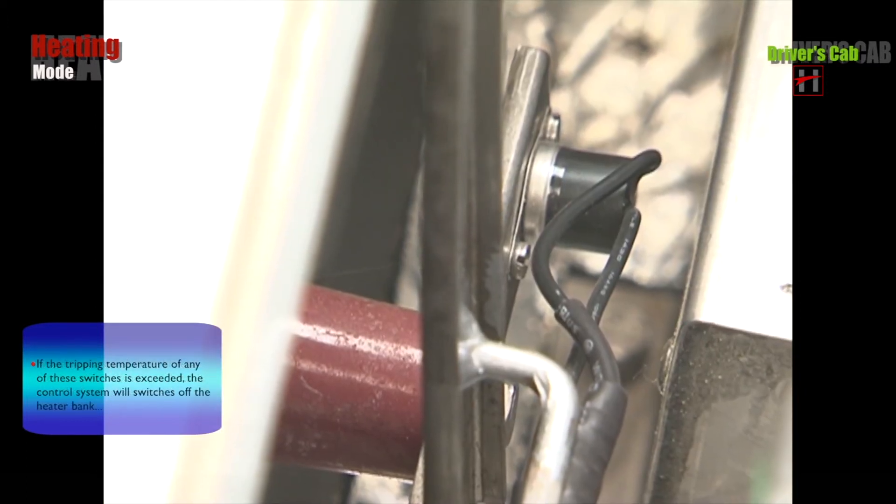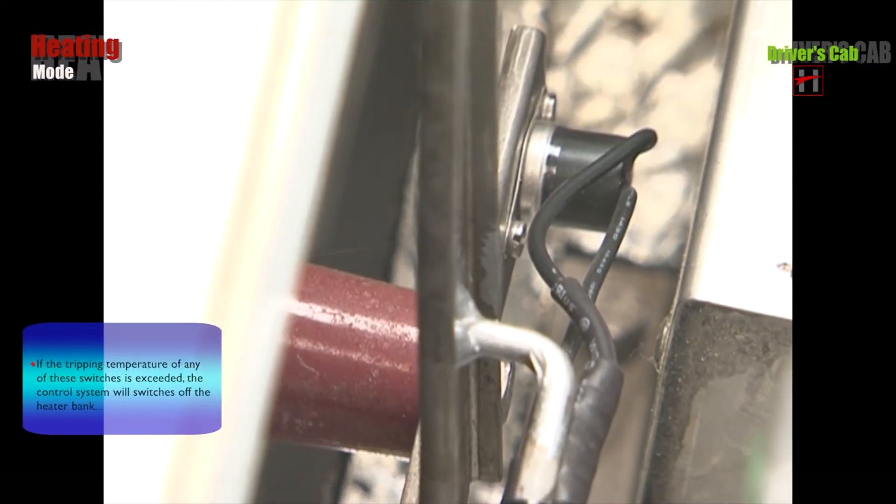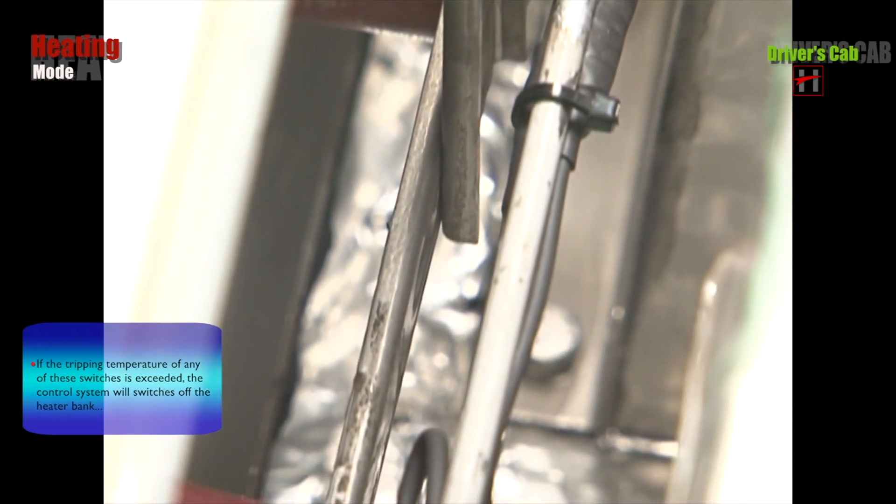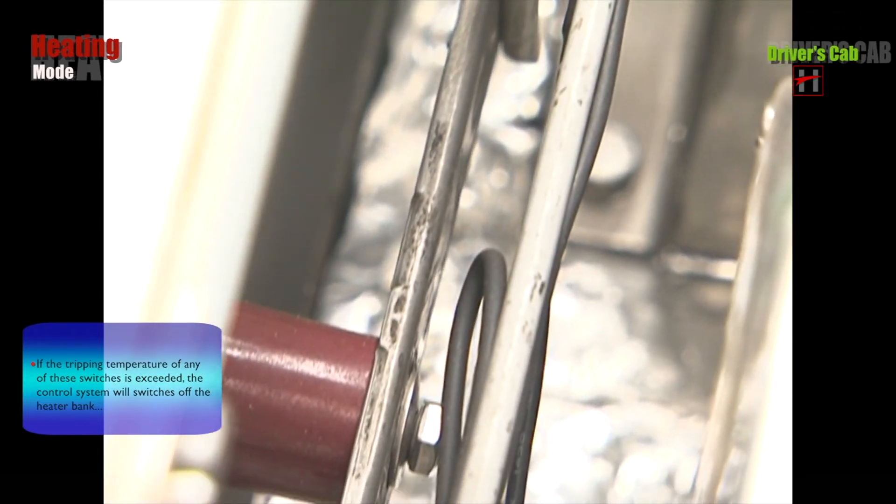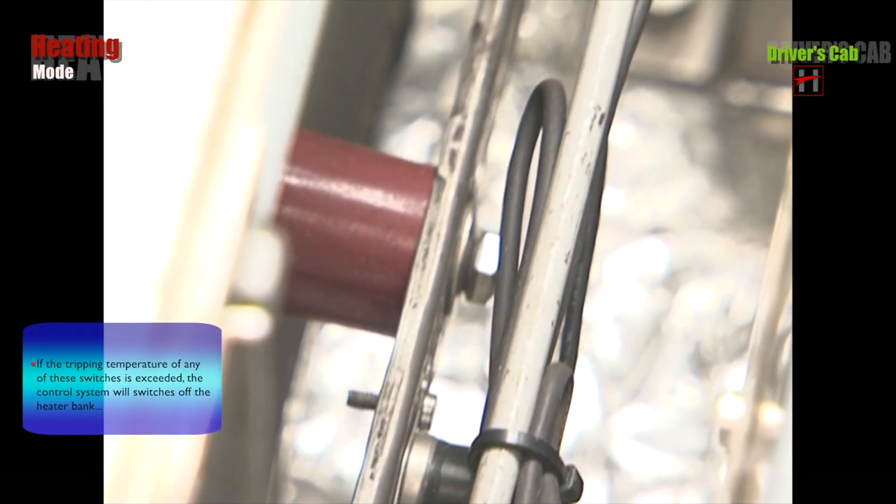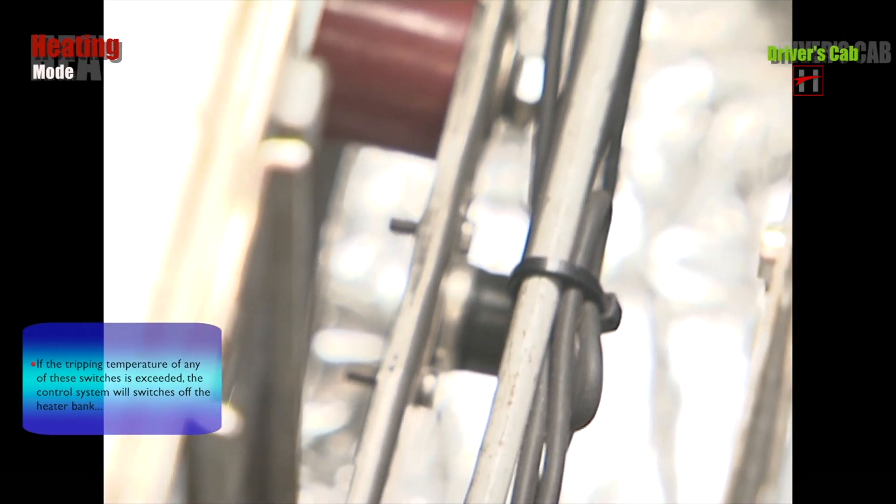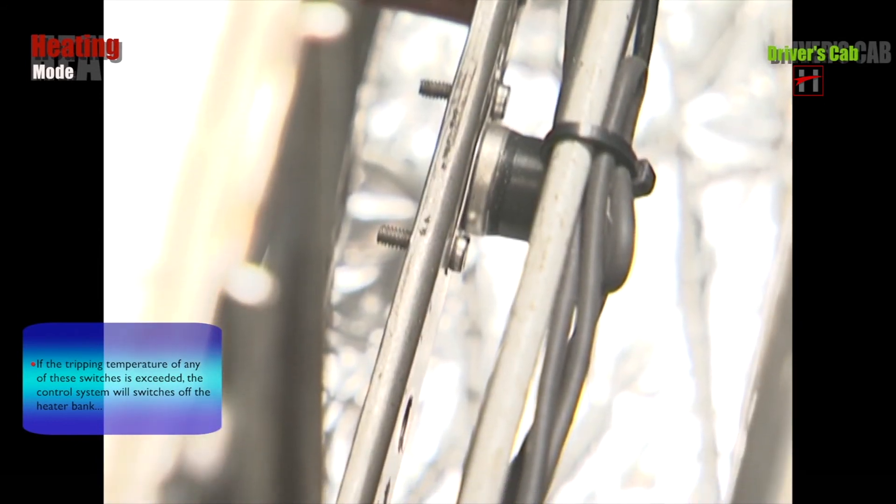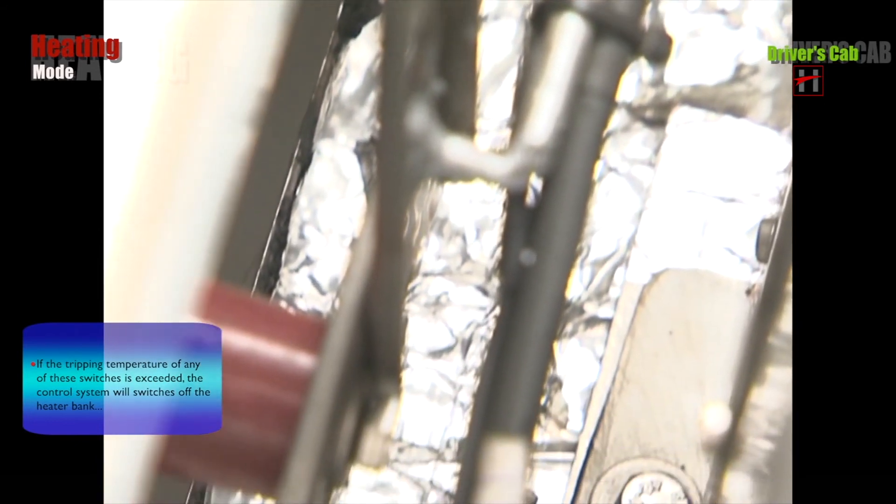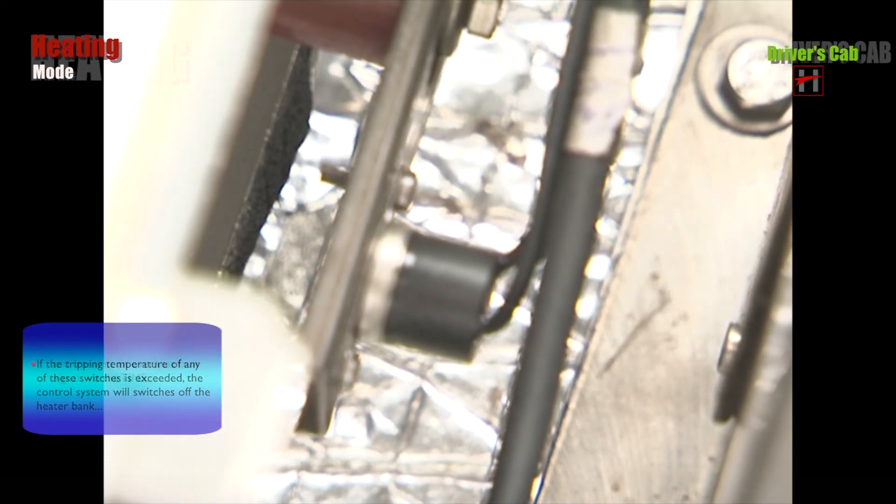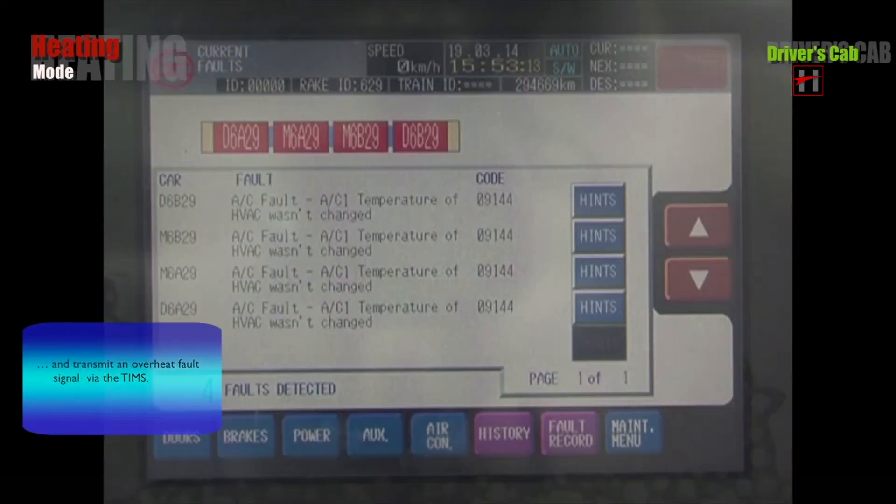If the tripping temperature of any of these switches is exceeded, the control system switches off the heater bank and transmits an overheat fault signal via the TIMS.